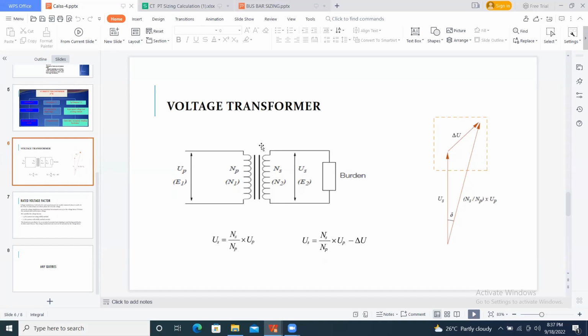Yes. So the voltage transformer, like a CT, or like a power transformer or auxiliary transformer, is where we step down the voltage from higher voltage to lower voltages. Because the relays connected to the secondary side of the voltage transformer are electronic devices, which are capable of handling only low voltages and low currents. But my system is 33 kV and 220 kV, so such high voltages cannot be withstood by this instrument. So obviously there should be a step down process from high voltages to low voltages. So here we require a potential transformer.